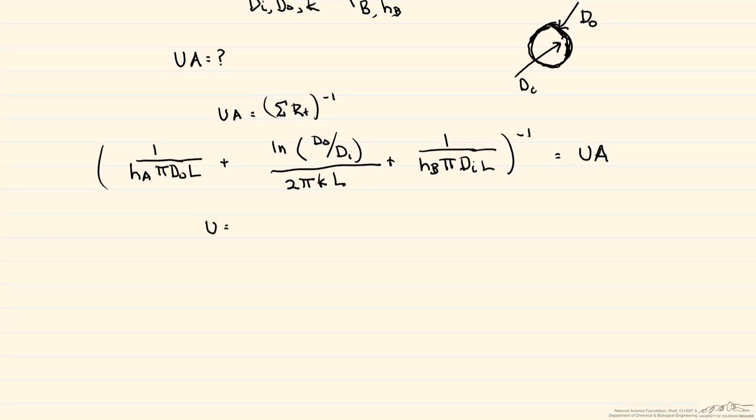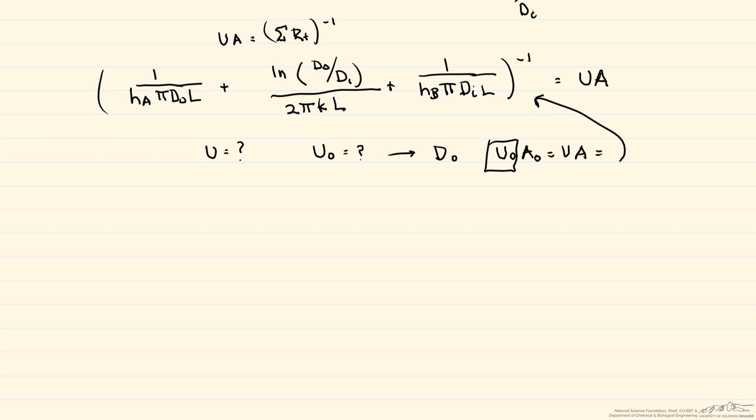So again, we want to find a U, and you can find it in terms of the inside diameter or in terms of the outside diameter. So let's look at it, and we write it here in terms of this outside diameter. And so what this means is that U outside times A outside is equal to UA, which is equal to what we had here. So basically what we're going to do is divide this expression that we put together by that outside area, and from that we get our U outside.